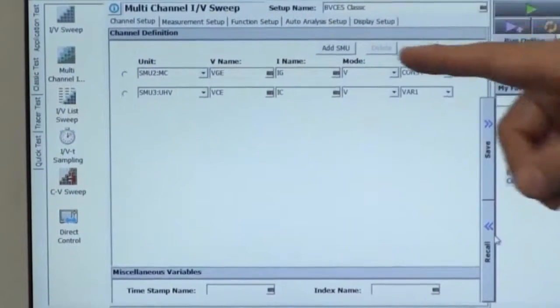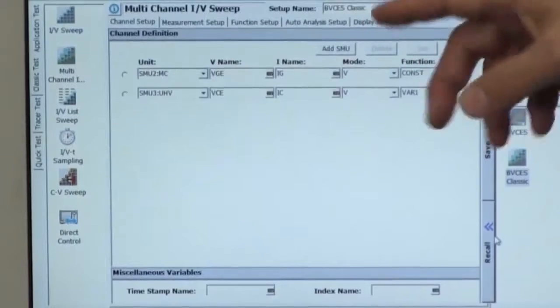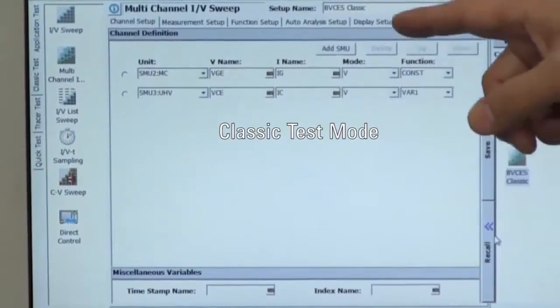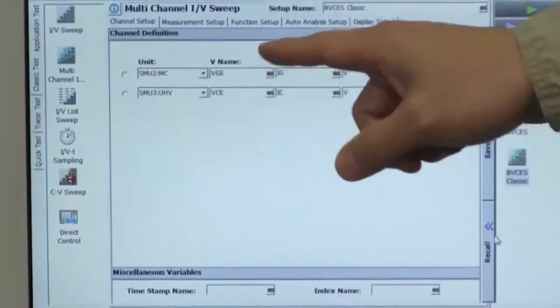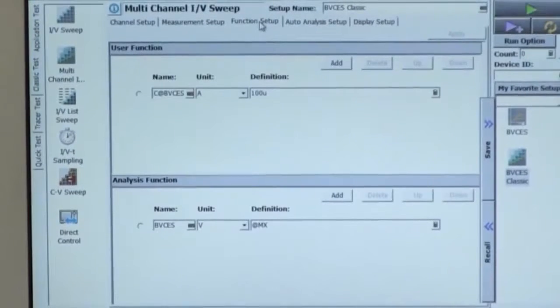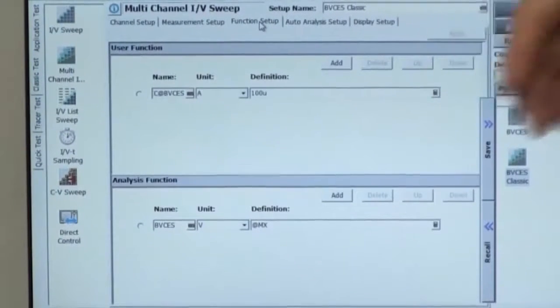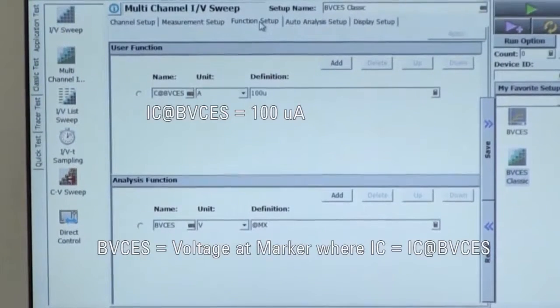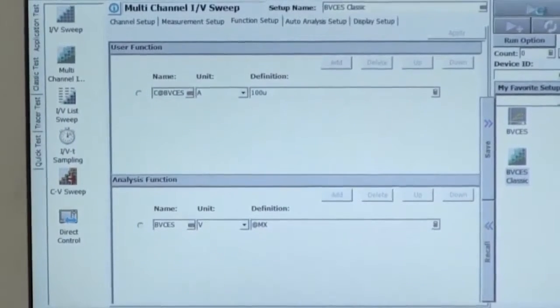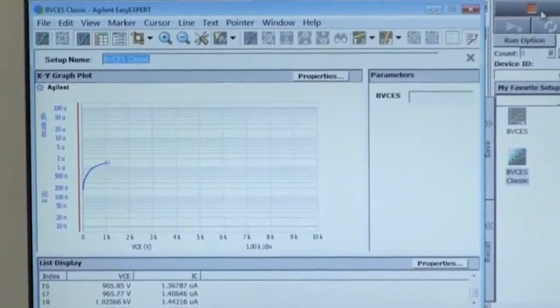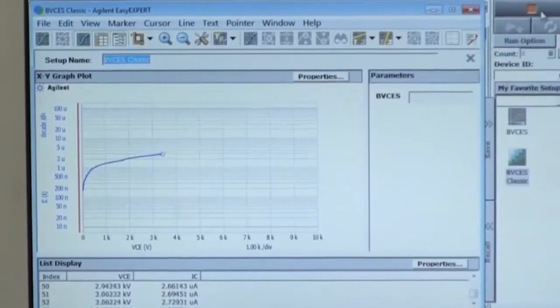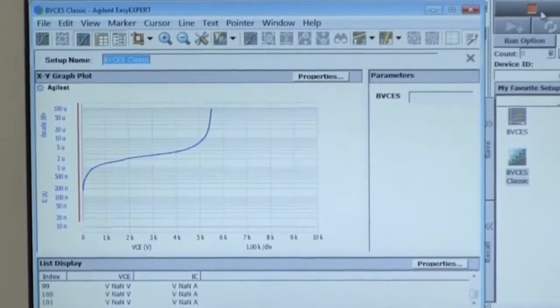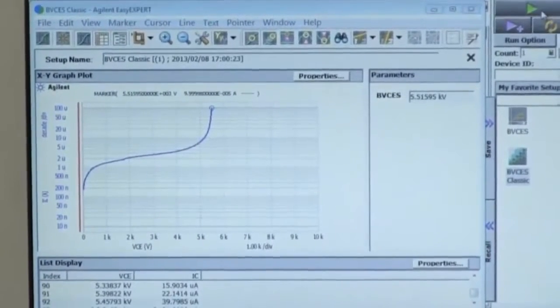So next, I'd like to show you a breakdown voltage measurement by using the classic test mode. In the classic test mode, it has an auto-analysis function to extract specific semiconductor parameters automatically. So by using these functions, B1505A can measure breakdown voltage at the specified current automatically.